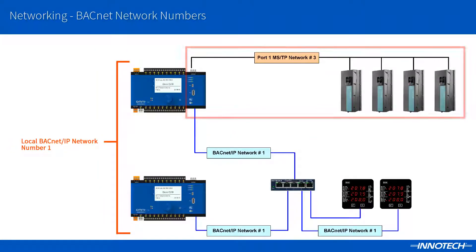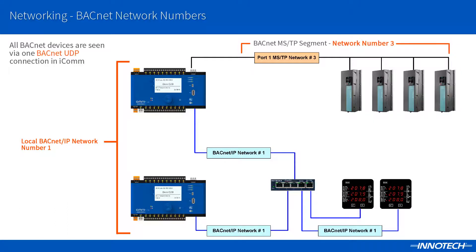If we connect an MSTP network to the Omni controller, we essentially have created a new BACnet segment, which requires a unique network number to be set. When the port is activated as MSTP, the network number defaults to 3. This is due to the fact that numbers 1 and 2 are already in use for the local and public networks.